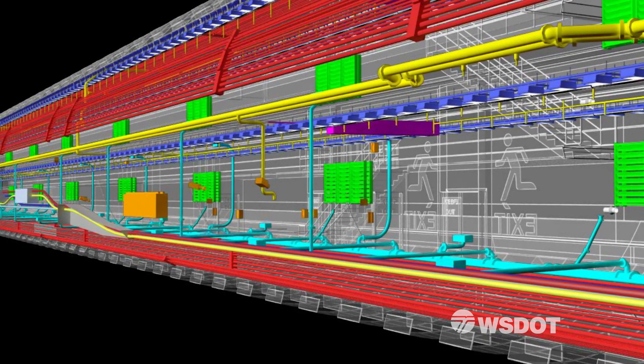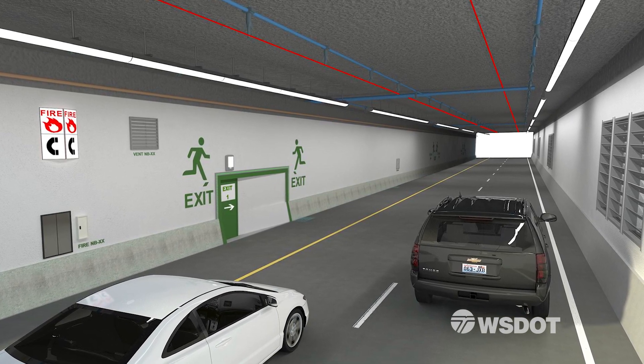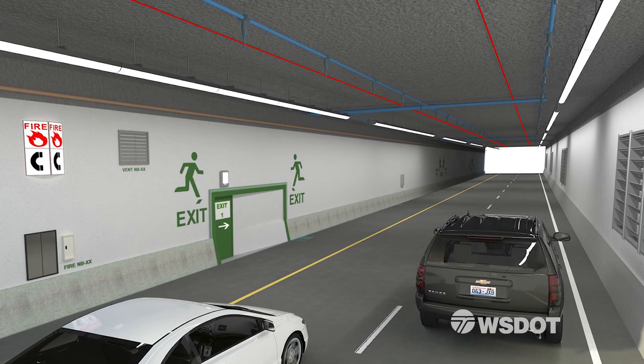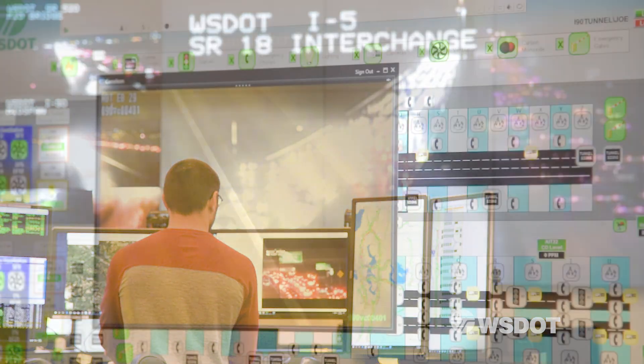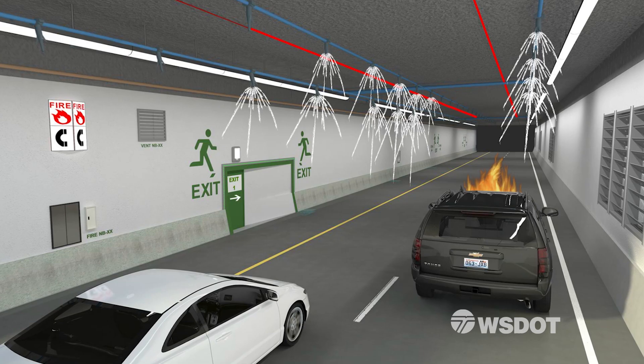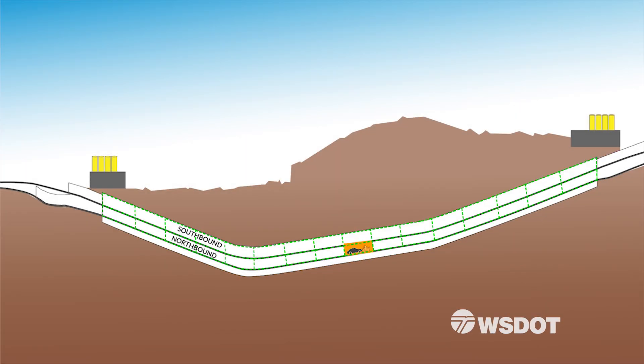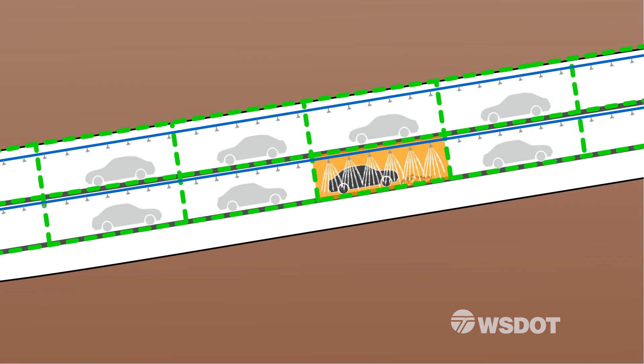The fire suppression system is another. More than eight miles of fiber optic heat sensors line the tunnel ceilings. If the sensors detect heat, they activate the fans and alert tunnel staff. A live camera shot then pops up on the tunnel operator's screen in the WSDOT Traffic Management Center. If there's no fire, the tunnel operator stops the sprinklers from turning on. But if there is a fire, sprinklers activate over the fire. The tunnel is divided into more than 100 safety zones that allow this kind of targeted response.